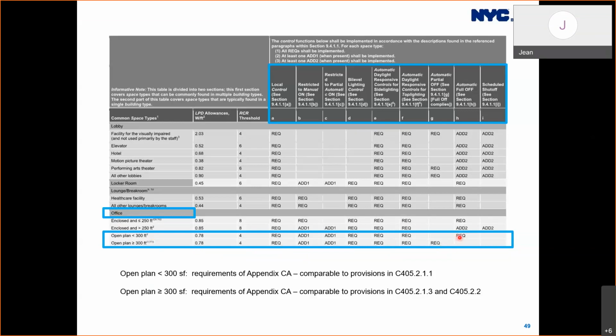The smaller open plan office area, general lighting must be automatically turned off, 100% full off, within 15 minutes of all occupants leaving. Whereas the general lighting in 300 square feet or greater must be automatically reduced at least 80% for ECC and at least 50% of the full lighting power for ASHRAE within 15 minutes of no occupancy. So for these two different size open plan office areas, the comparable ECC sections are found here, and they're almost identical.